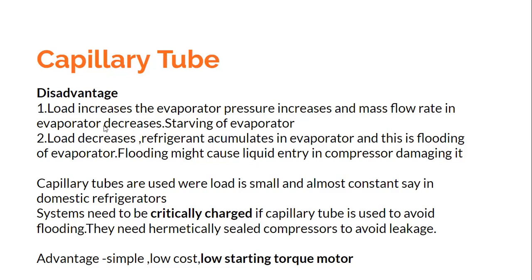Similarly, when the load would decrease, the refrigerant would accumulate in the evaporator, and there is a flooding of the evaporator. It means that in response to the load changes, the evaporator either would be starved of the refrigerant, there would be less refrigerant in the evaporator, or it would be flooded with the refrigerant. That is, there would be excess of refrigerant in the evaporator.